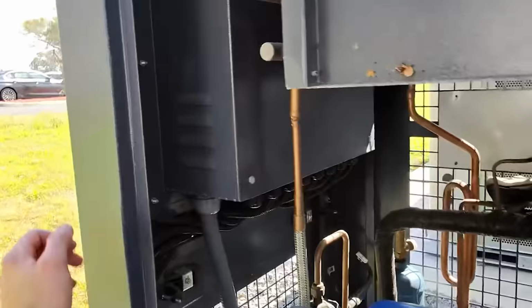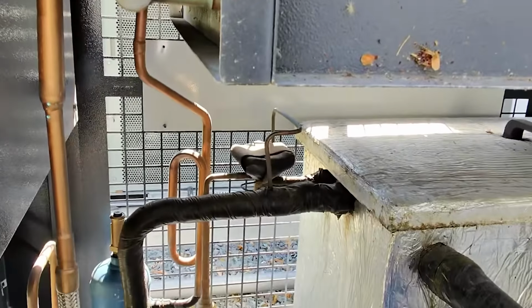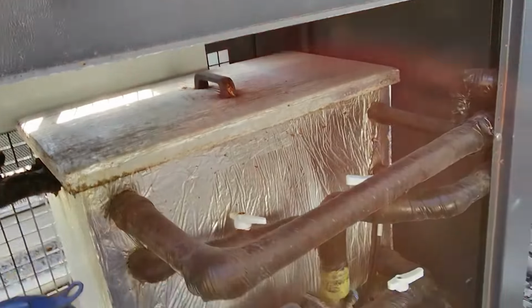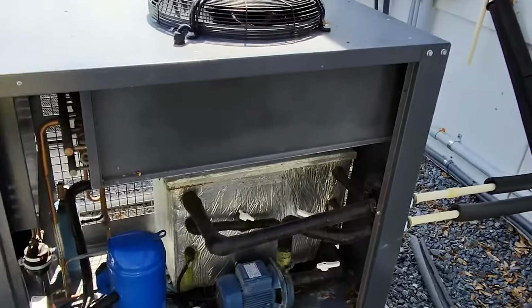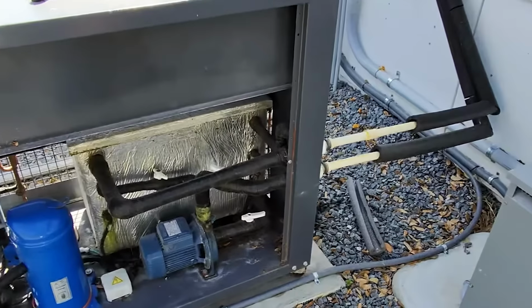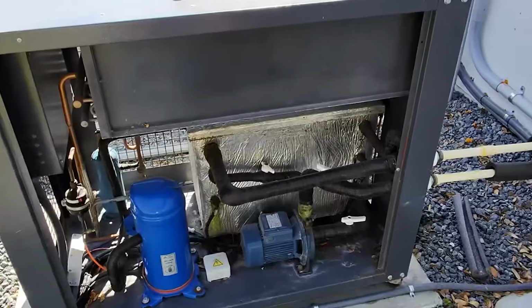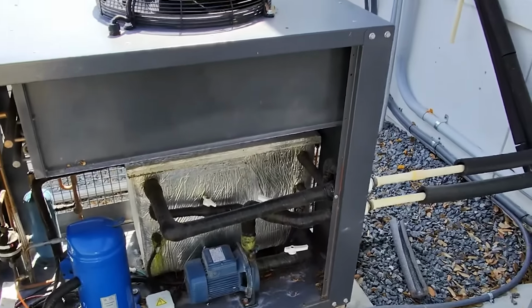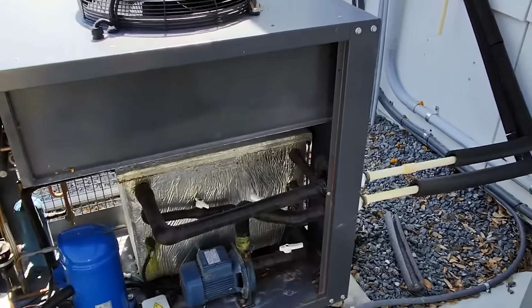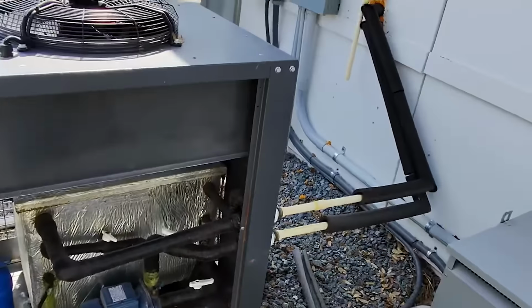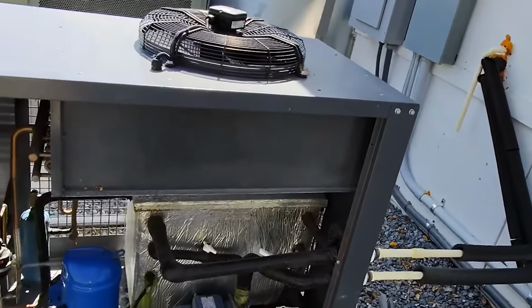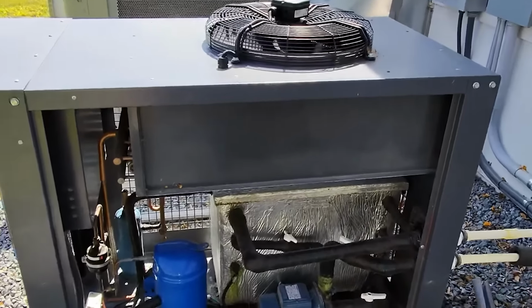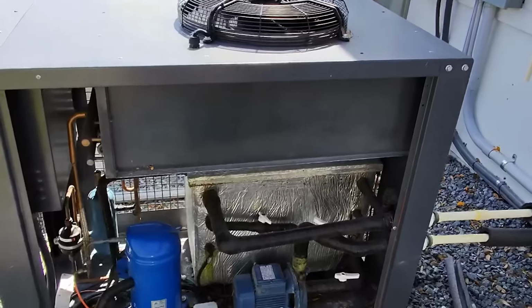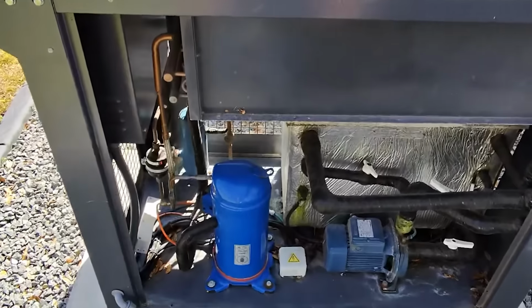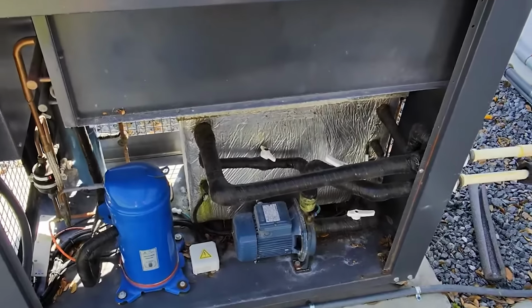The bearings in this pump don't sound the best, which you can actually see if I turn this on. So we are removing heat from inside, and inside looks good. They said they tied into it remotely. I guess they have access to it over the internet. What they're saying now is that's something to do with the outside system, and I believe it. So water pump will run, circulate water inside, remove the heat. Water gets really hot. This compressor will not run for more than 2 minutes, so we need to investigate to see what's going on there.